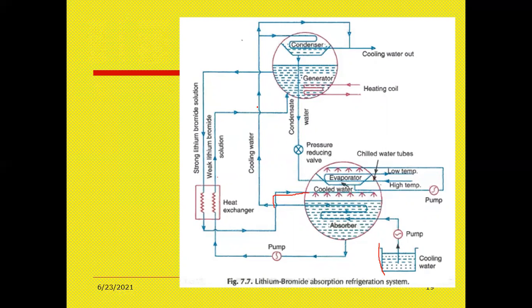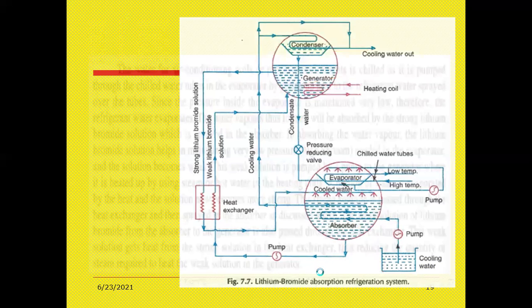The cooling water is passing into this chamber and it is going into the condenser. Where the cool water is going out, this generator makes the water heat at this point, and the water is going through the pressure reducing valve to this evaporator, and it is passing into this absorber for heat exchange again. So this is the process happening in this lithium bromide absorption refrigeration system.